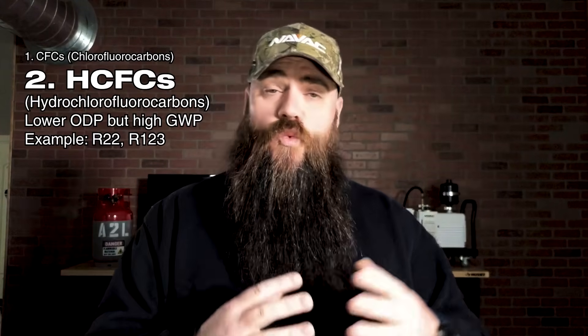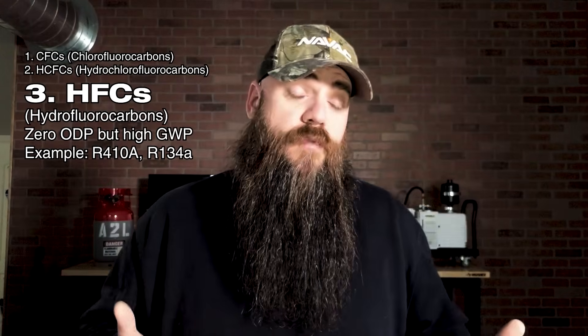With the development of HCFCs — hydrochlorofluorocarbons — which would include refrigerants like R22 and R123, we were able to lower ODP, but we still had a very high global warming potential. Now, at the turn of the century, the Y2K era, we saw more improvements with HFC refrigerants — hydrofluorocarbons. This changeover was dominated by the emergence of R410A and also refrigerants like R134A. The changeover to HFCs actually brought our ODP to zero — another big improvement — however, GWP still remained high.